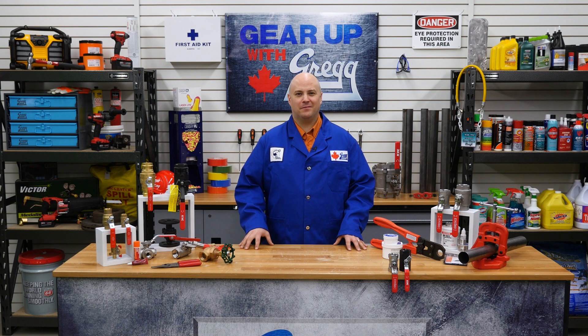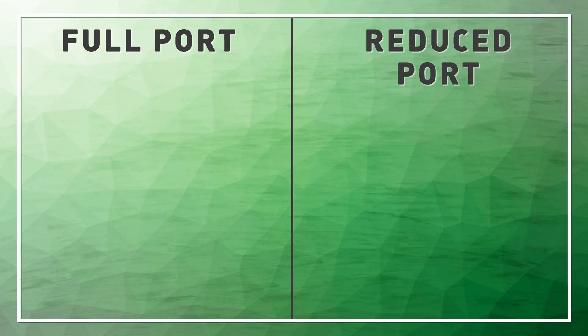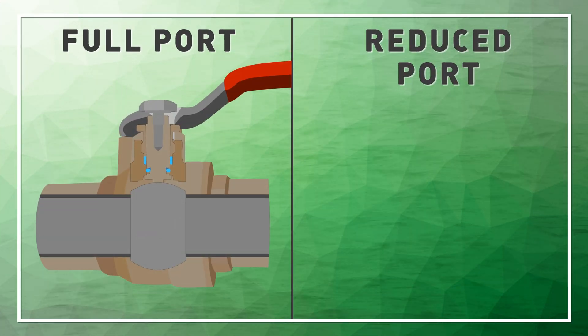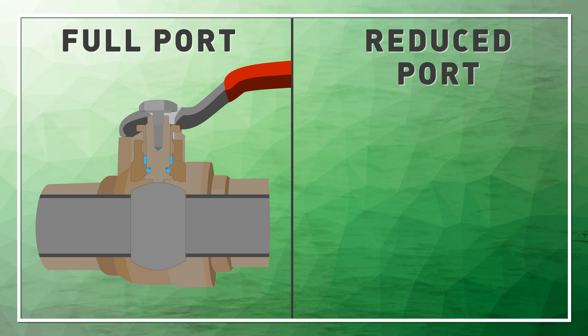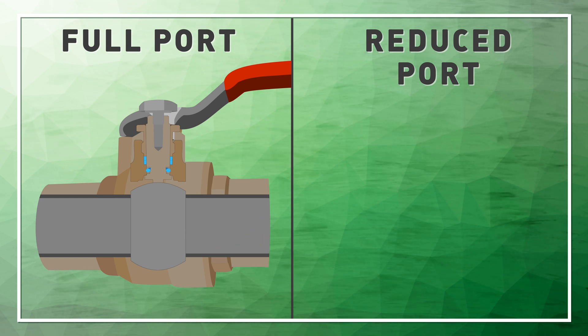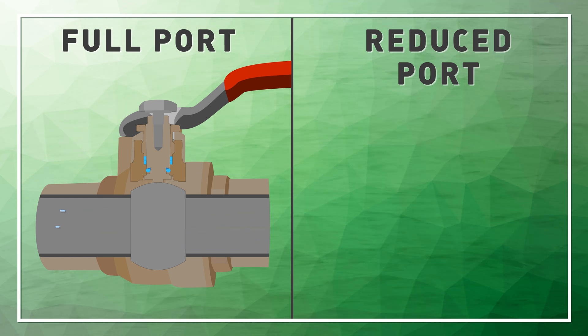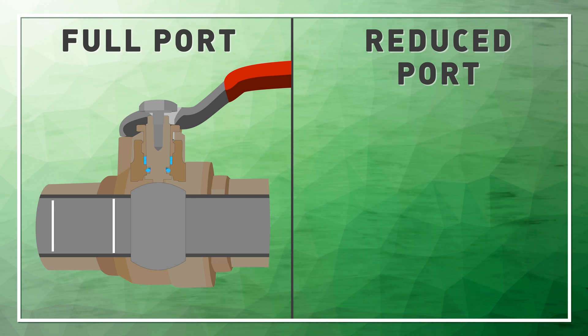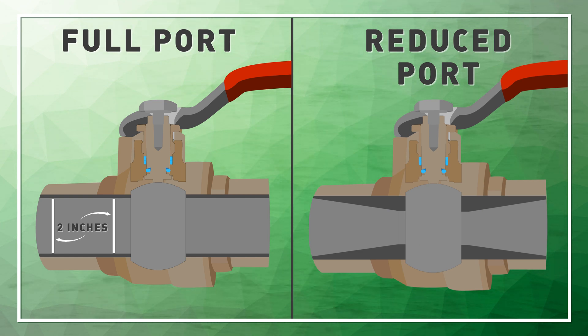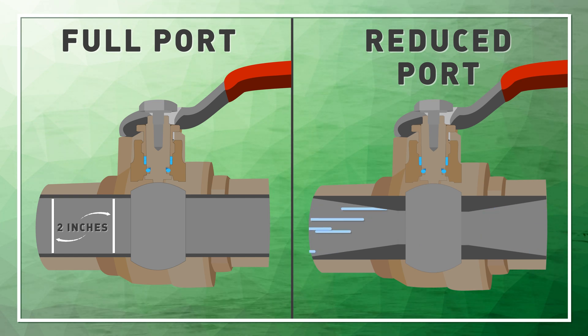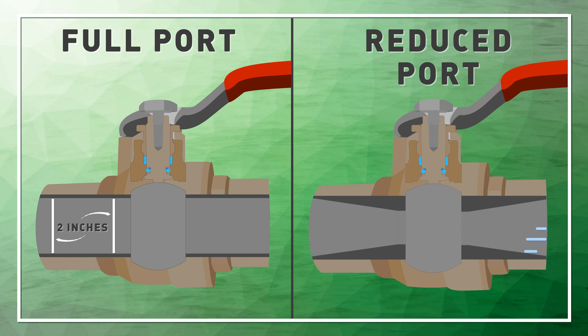When speaking about valves, you'll often hear the terms full port or reduced port. A full port valve means that when you connect a pipe or a hose to your valve, there will be no restriction of flow from the original diameter. So if the measurement of the IDs are equal, then it is a full port valve. A reduced port valve measures a smaller ID than its connection.